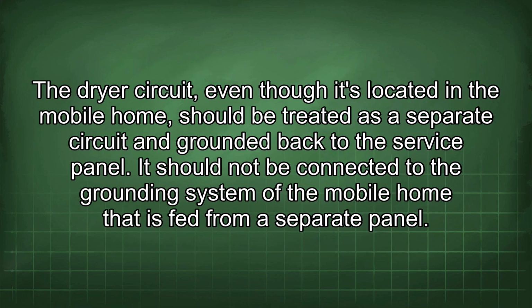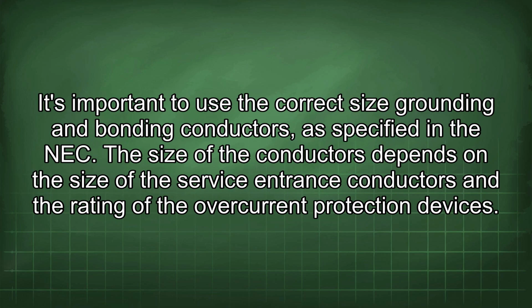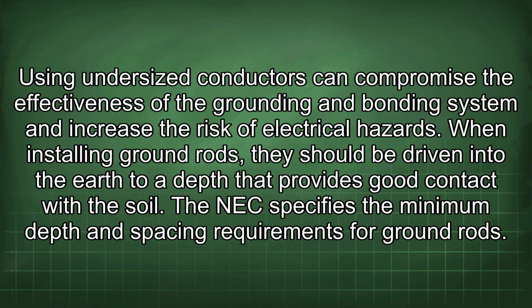The dryer circuit, even though it's located in the mobile home, should be treated as a separate circuit and grounded back to the service panel. It should not be connected to the grounding system of the mobile home that is fed from a separate panel. It's important to use the correct size grounding and bonding conductors as specified in the NEC. The size of the conductors depends on the size of the service entrance conductors and the rating of the overcurrent protection devices. Using undersized conductors can compromise the effectiveness of the grounding and bonding system and increase the risk of electrical hazards.